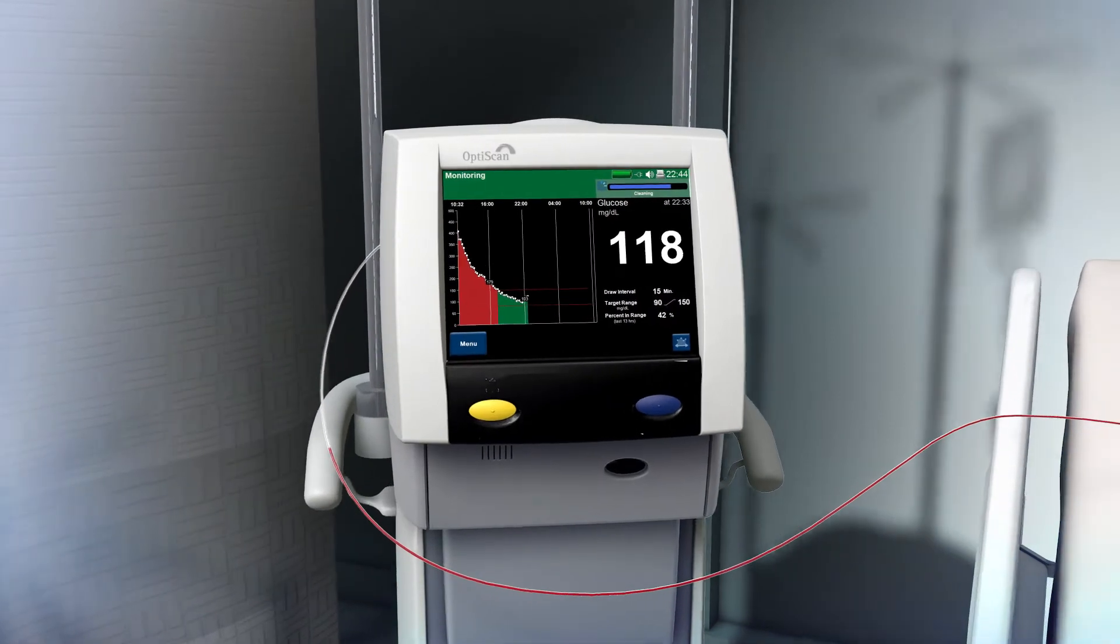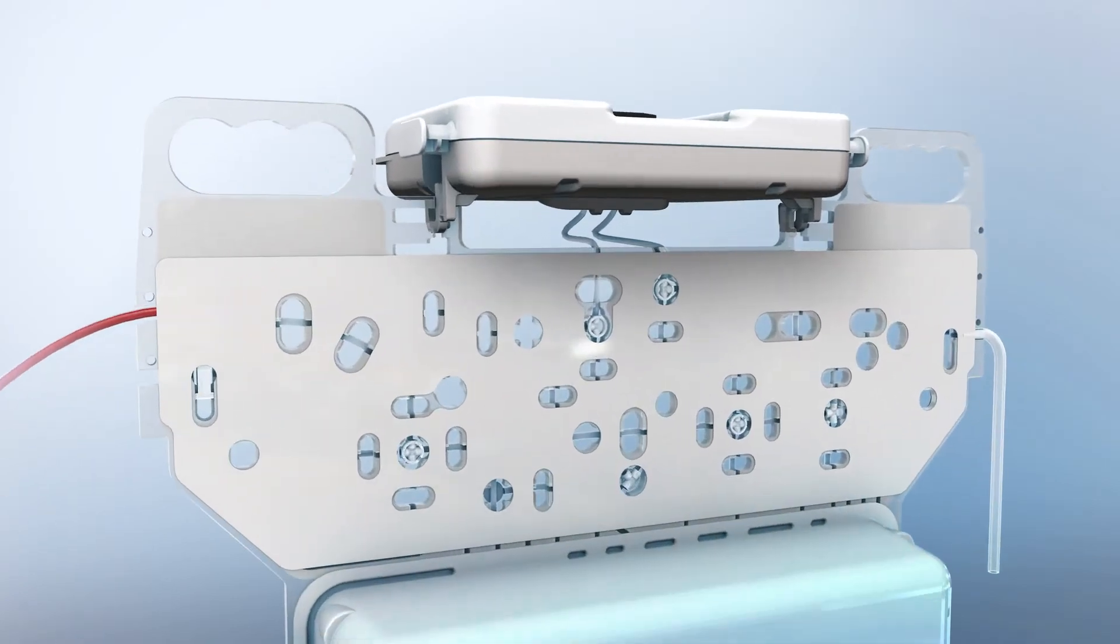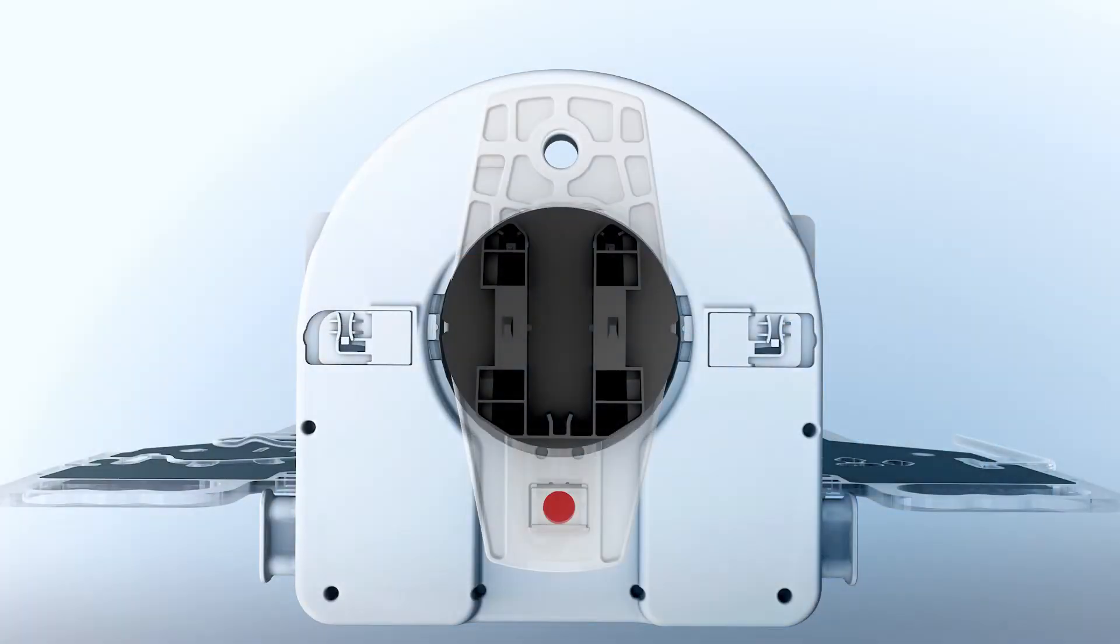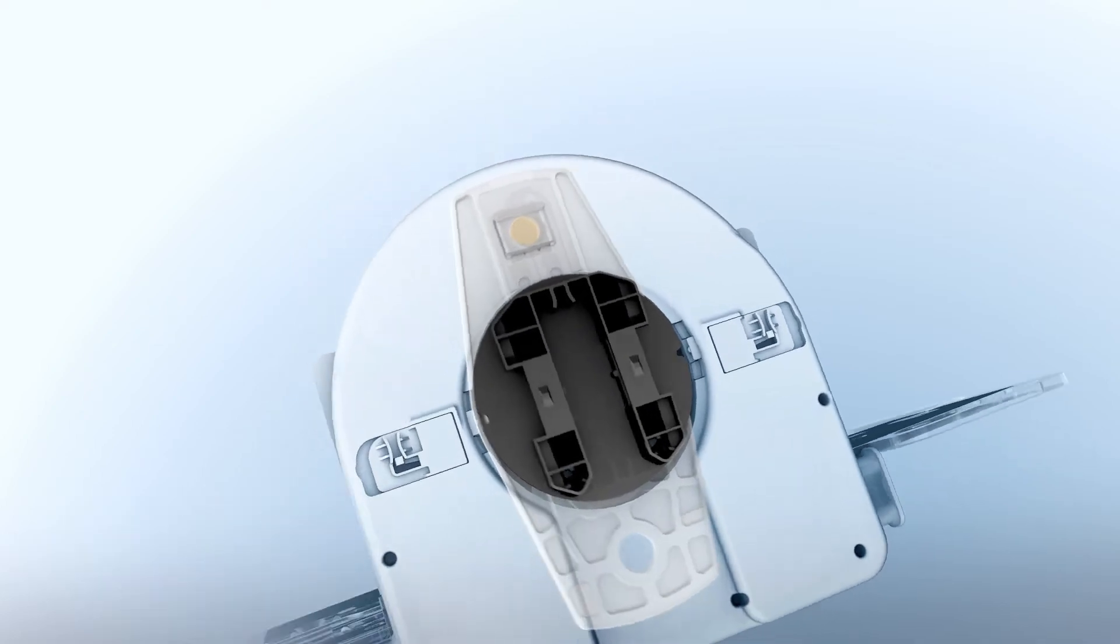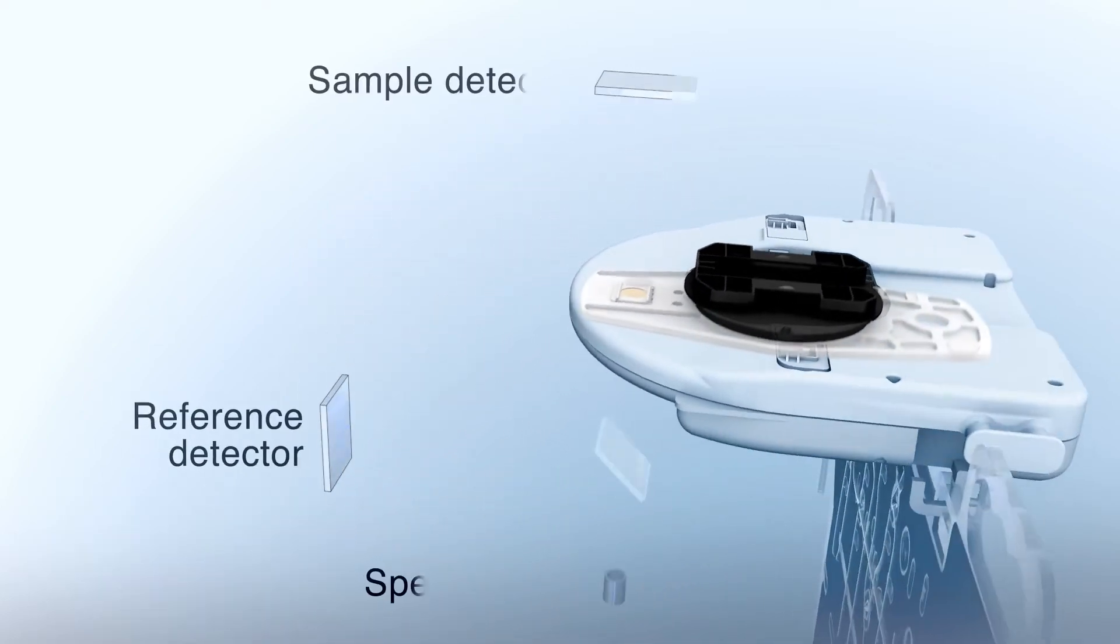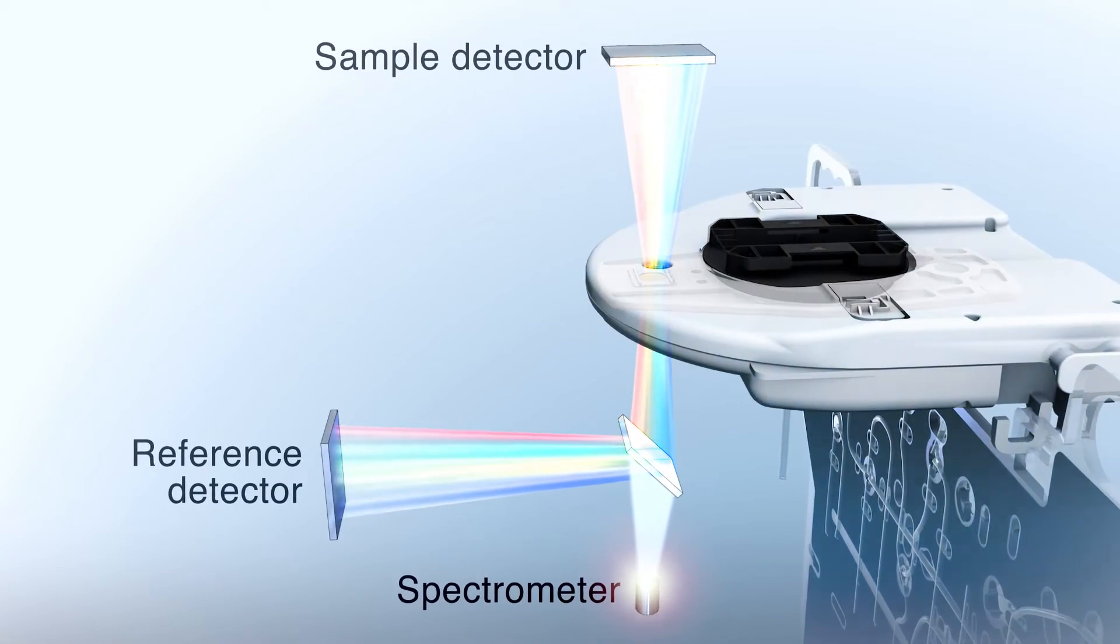The OptiScanner automatically draws blood every 15 minutes. A microsample of blood is isolated and heparinized within the disposable cartridge, where it is centrifuged to separate plasma from other blood components. The spectrometer measures blood glucose directly from the plasma sample without the need for calibration.